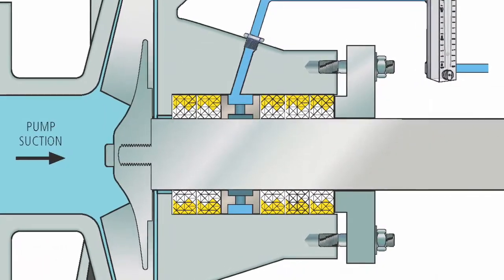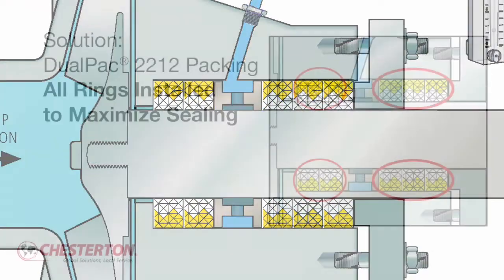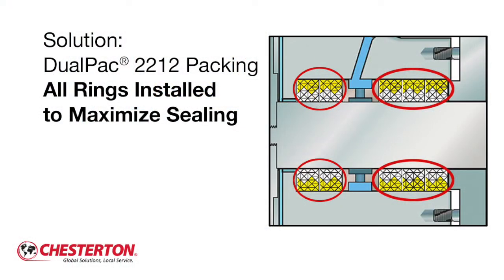In applications where packing extrusion and solids abrasion are not issues, install DualPac 2212 with a five seal ring configuration. In this configuration, all rings are oriented with the white meta aramid fiber contacting the shaft to minimize leakage.